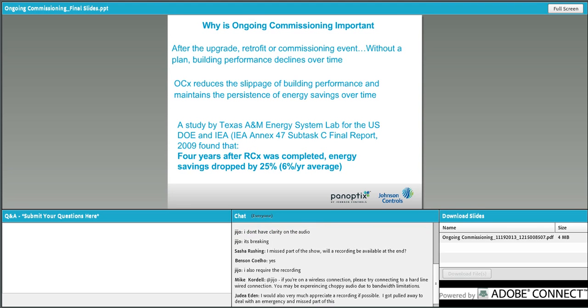And that degradation is due to a multitude of problems, ranging from faults such as manual overrides or reset schedules, leaking control valves, inoperable economizers, and a wide range of deferred maintenance issues. A study by Texas A&M in 2009 determined that an average energy saving of 6% per year is lost due to slippage in system performance after a commissioning event. And yeah, I think that's very conservative.